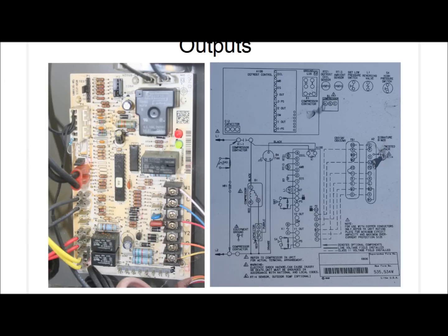And then we have another set of terminals, which are the red ones down here in the bottom left. This is what turns the contactor on, that when it's energized, it turns on the condensing unit. So in a more simplified manner, what will happen is 24 volts comes in on the Y terminal, finds its way through the control board, and out it goes to the contactor to energize the contactor and turn on the compressor and condenser fan motor when there's a call for cooling. Now there's a couple more terminals here. The black terminals and the yellow ones, those are high and low pressure switch controls.